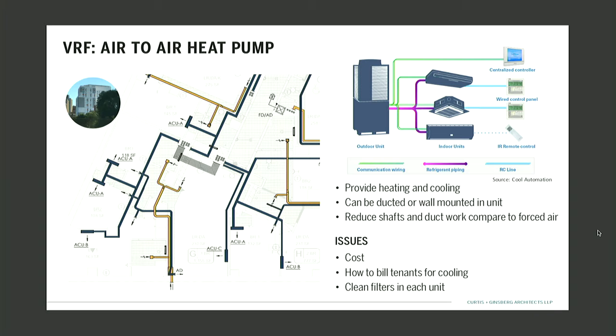So VRFs are great. The other issue with VRFs is each unit has a filter. The filter needs to be cleaned every 6 months. That means that the super has to get into the apartment every 6 months. And when we talk about unitized ERVs, we have the same thing. The final issue with VRFs is that the landlord has to pay for heat. At least all of our projects have been affordable housing. The landlord doesn't want to pay for cooling. The tenant can pay for it or not. Well, with a VRF, you can put a BTU meter on them. So that's what we've done. But that costs money, and you have to hire a company to monitor it and so on. And then what happens if the tenant doesn't pay? It isn't like Con Ed where you can shut off the power. The landlord has to take the tenant to court. And now when you look at the costs and so on, that becomes a problem, because if the tenant doesn't pay, it probably isn't worth going to court. And so the landlord is sort of caught in there.